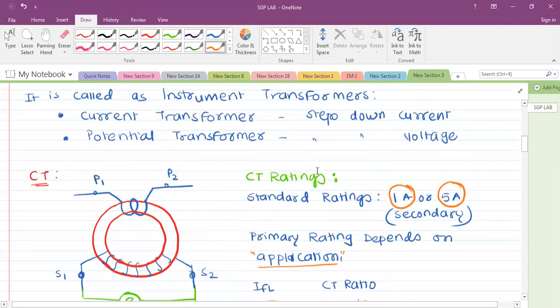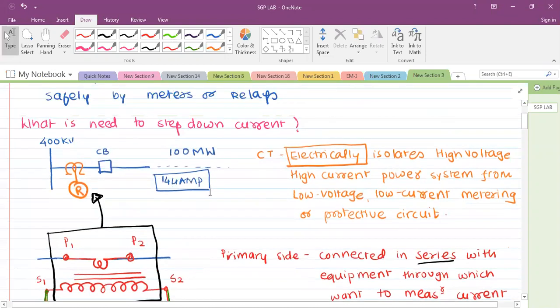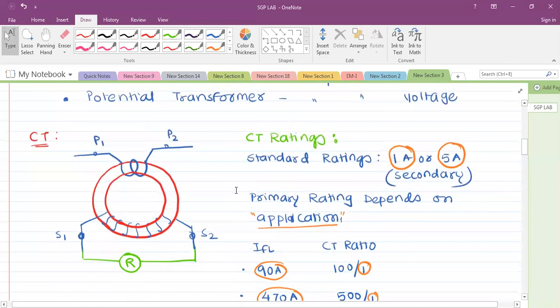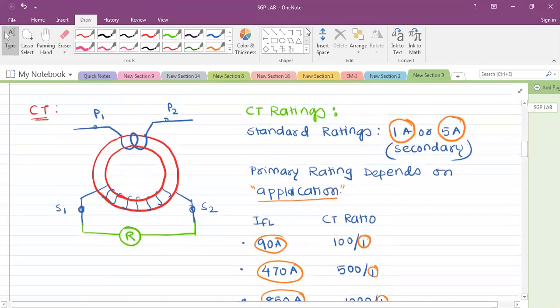For example, in this line we calculated that the primary current is 144 ampere, so we can go with a CT of 200/1 for this application. Understand this point about CT ratings - we are not talking about any other specification at the moment, only the current rating of the CT. So now onwards, remember that CT secondary ratings can be either 1 ampere or 5 ampere.